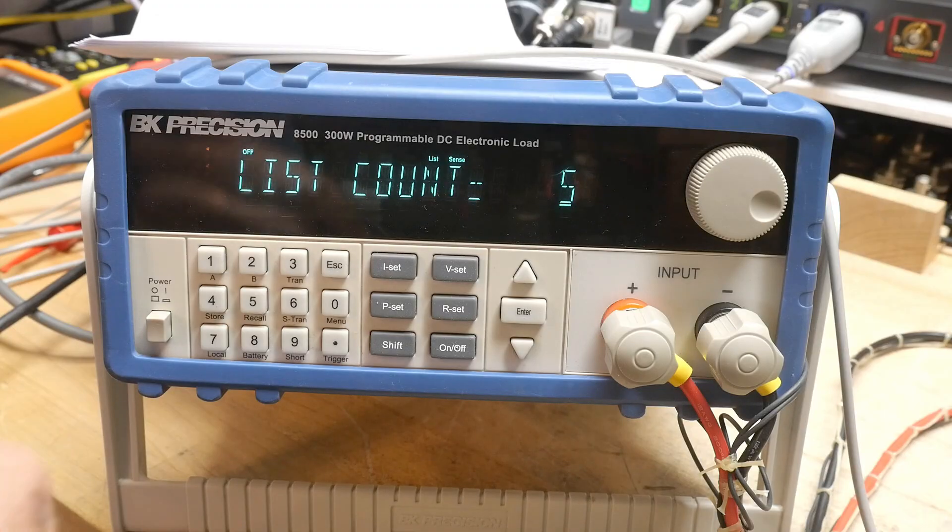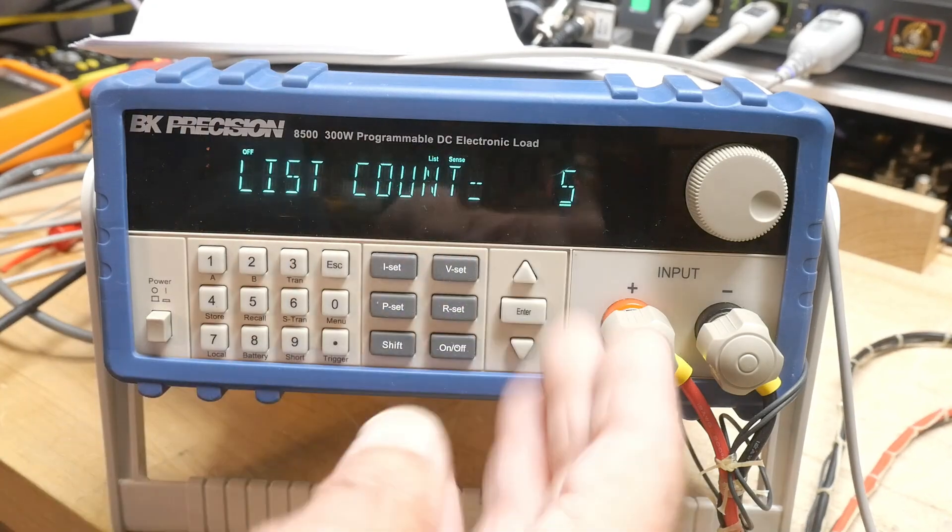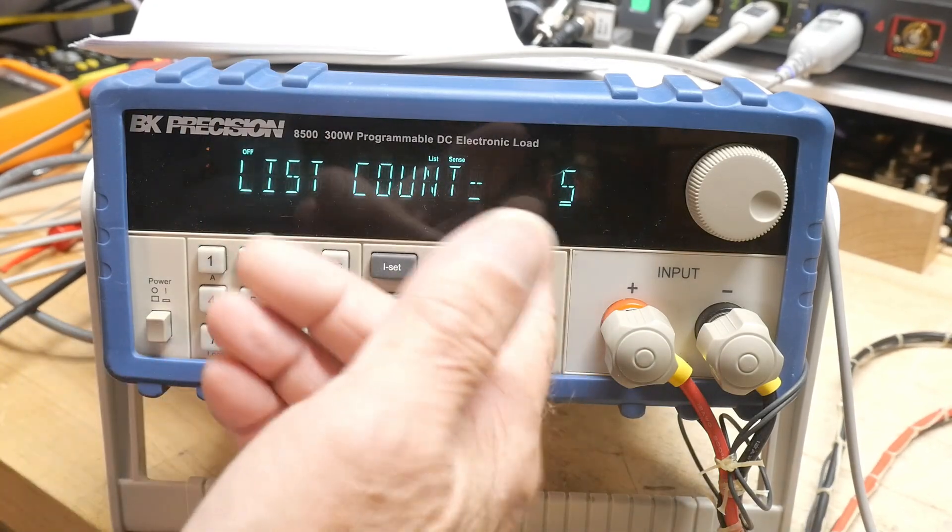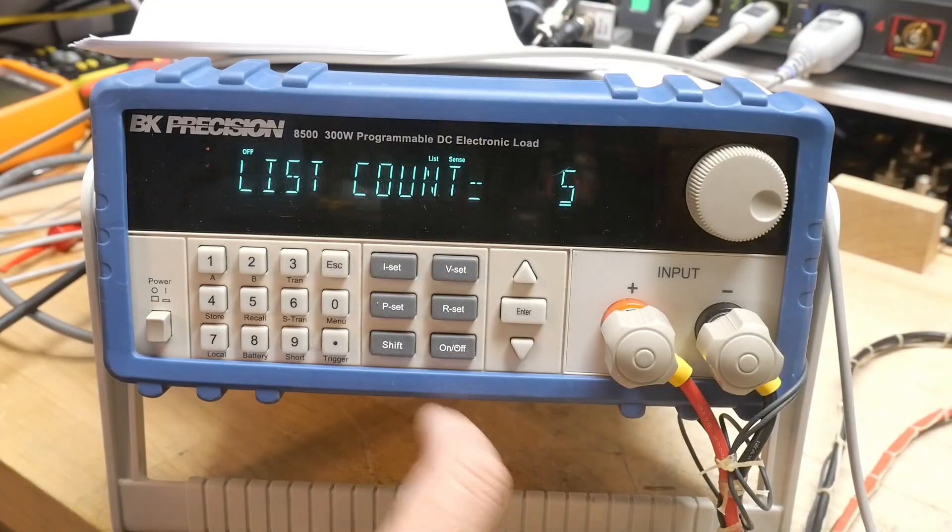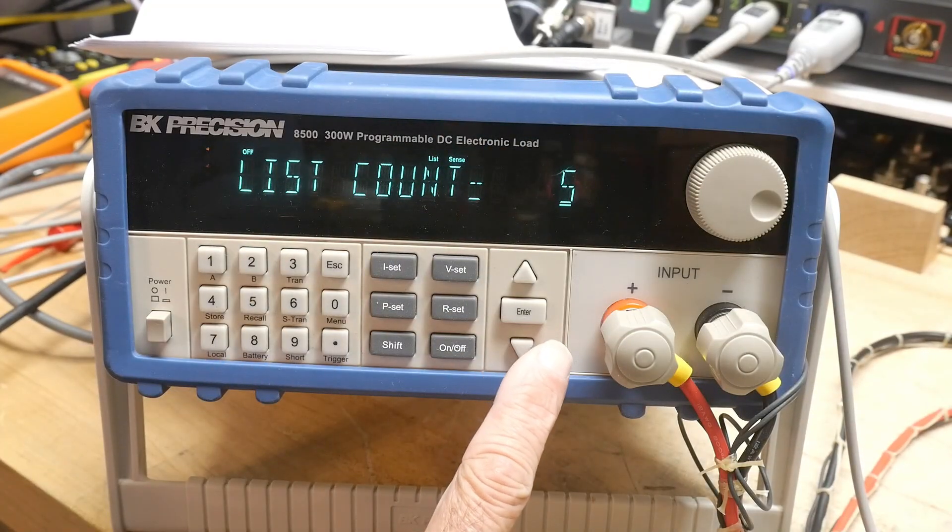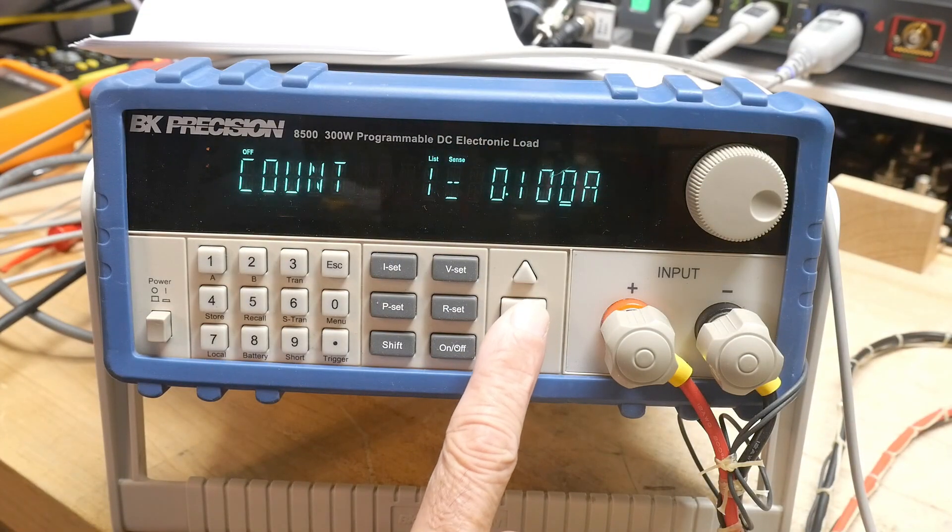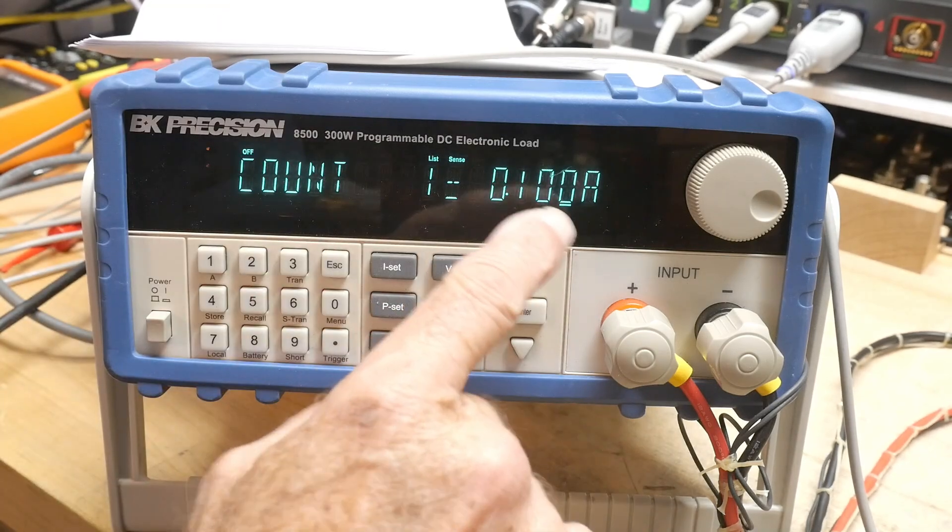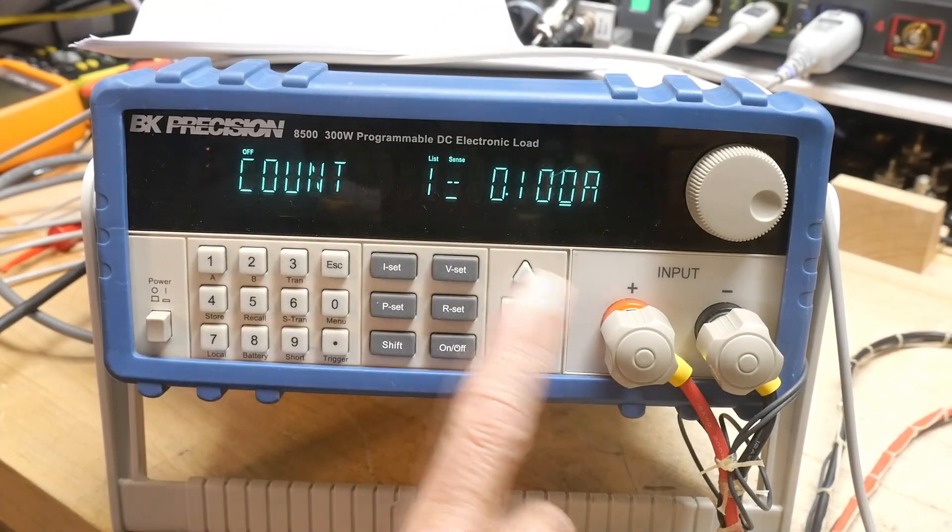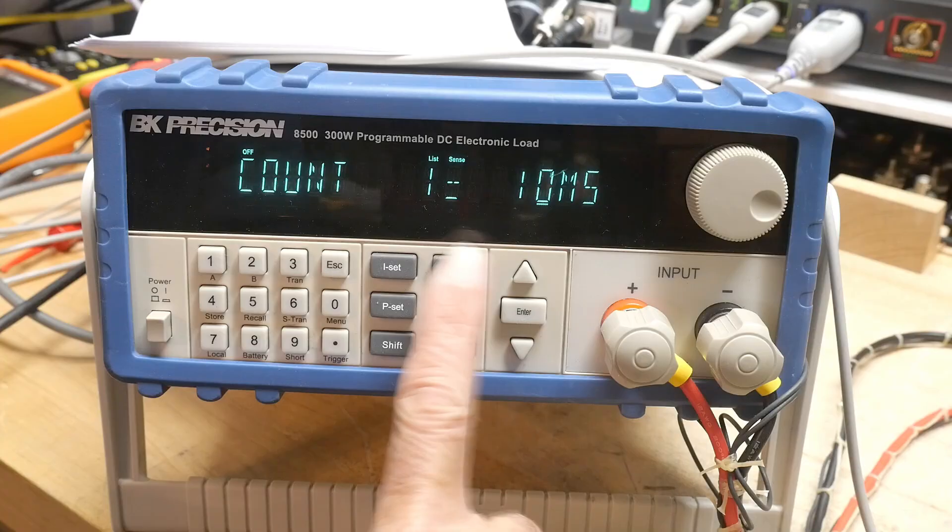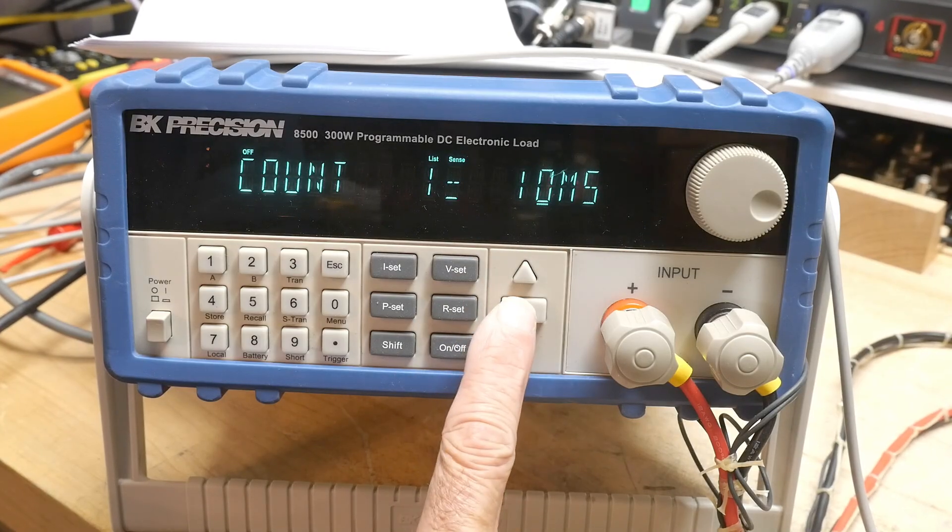So you can create a list of numbers and here we have five numbers. You can say at the very beginning what current do you want - 100 milliamps. And I'm going to hold that 100 milliamps for 10 milliseconds.